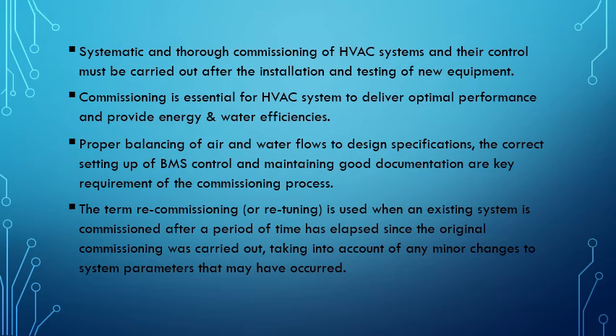We also must make sure we have a very good and proper balancing for the air and water system. For the air system, we usually refer to the ducting system and the diffuser, and the water system refers to the chiller and the chilled water system that goes into the air handling unit and FCU. It refers to the good design specification and correct setting for the building management system control, to make sure we maintain good documentation. So this is the key to a good commissioning process.